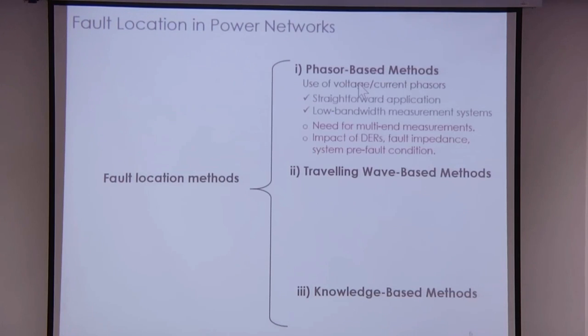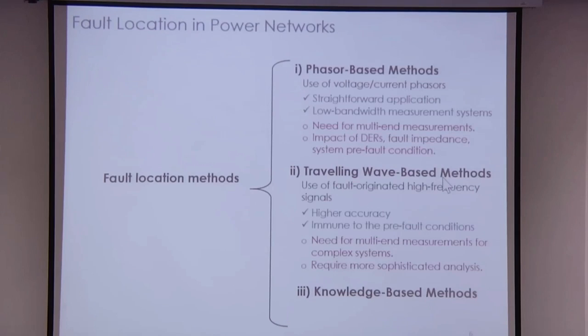However, their performance might be affected by many conditions, like pre-fault condition or fault impedance. Therefore, we decided to use traveling wave-based methods. So instead of measuring 50 hertz, we measure high-frequency signals. So they are more reliable, more accurate.